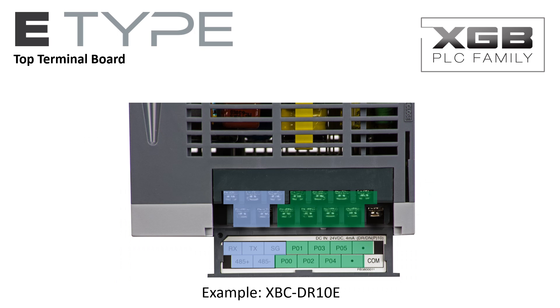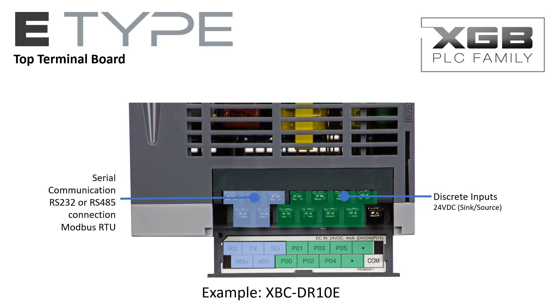The top terminal board provides connectivity to the serial communications port. This port may be wired as an RS-232 or RS-485 port, and can be configured for Modbus RTU, LS-dedicated, or user-defined protocols. The PLC's discrete inputs are also on the top terminal board; the inputs are 24V DC and can be wired as sink or source inputs.